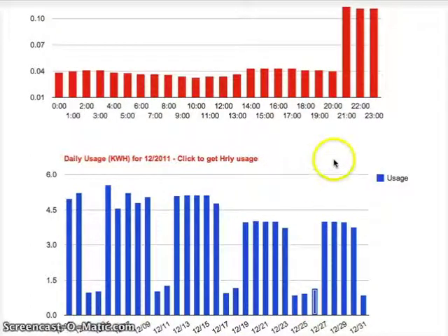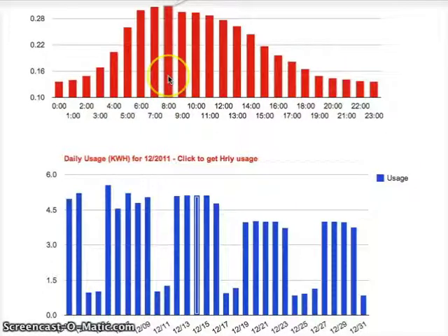In Step 5, we come back to the maximum load to ask when this maximum occurs during the day. Some utilities charge higher rates in the afternoon when demand is highest, and as a result, businesses can save money by shifting activities earlier or later in the day. For the building in this example, the peak typically occurs at around 8 a.m.